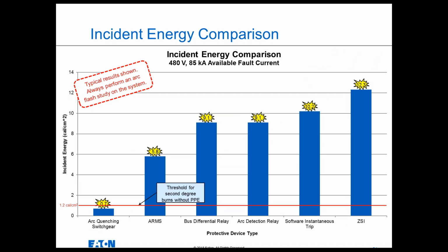Bus differential and arc detection relays. So just an arc detection relay tripping a main, not tripping the arc quenching device, comes in at about 9.1. Eaton's energy reducing maintenance switch, which is called ARMS, comes in at 5.8. It's lower than an instantaneous because it actually uses a parallel analog trip circuit, so it's not relying on the electronics, the RMS voltage calculations and whatnot of the trip unit. It uses a parallel trip circuit, so it's significantly faster than instantaneous trip.